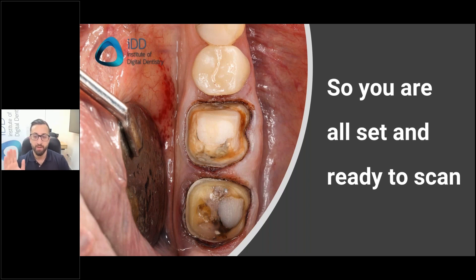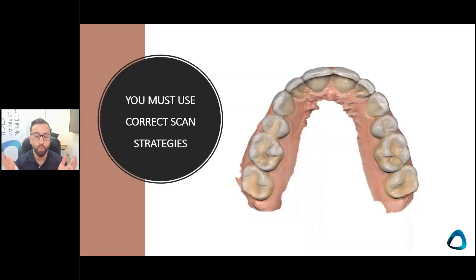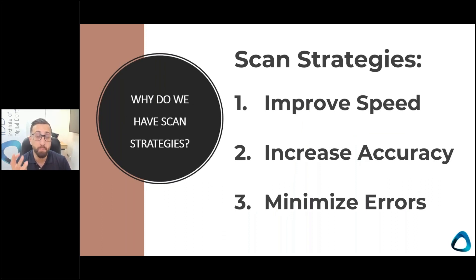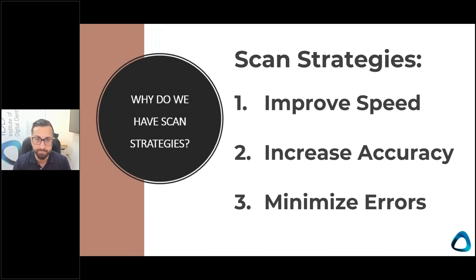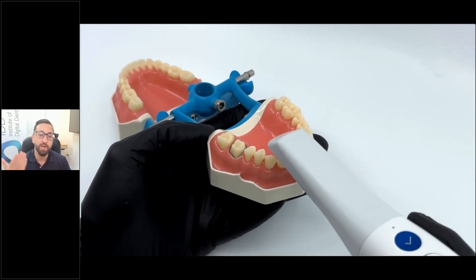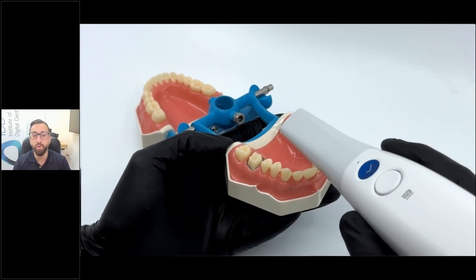Now you're set up with the scanner and computer and ready to scan. First and foremost, you need to use correct scan strategies. In the Medit software there is smart stitching and AI features, but without a doubt, using scan strategies improves your scan speeds, increases accuracy — this has been literature proven — and helps minimize errors. Rather than haphazardly scanning around, a continuous fabrication of the digital impression rather than stitching a lot of data together will improve accuracy. The occlusal scan first, then the palatal, then the buccal — or any variation of this — is how I do a scan in my office.